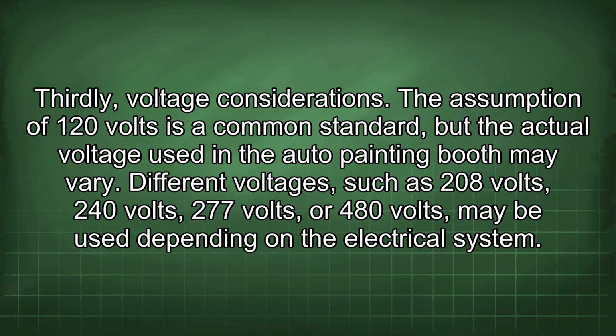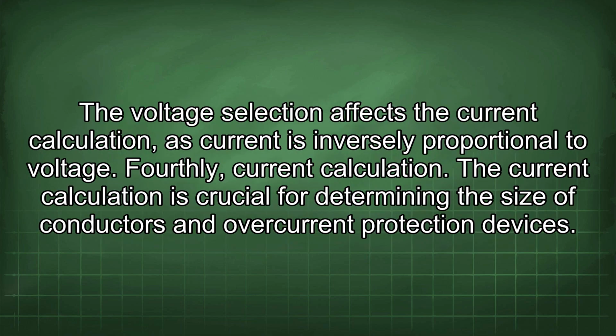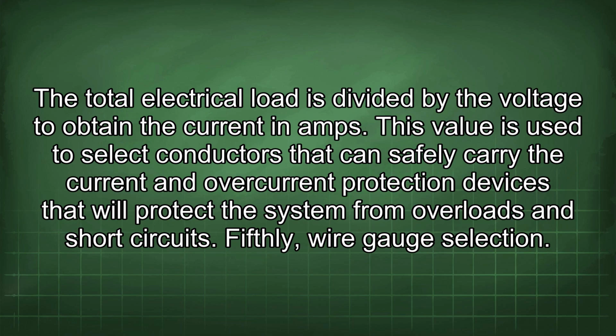Thirdly, voltage considerations. The assumption of 120 volts is a common standard, but the actual voltage used in the auto painting booth may vary. Different voltages such as 208 volts, 240 volts, 277 volts, or 480 volts may be used depending on the electrical system. The voltage selection affects the current calculation, as current is inversely proportional to voltage. Fourthly, current calculation. The current calculation is crucial for determining the size of conductors and overcurrent protection devices. The total electrical load is divided by the voltage to obtain the current in amps. This value is used to select conductors that can safely carry the current and overcurrent protection devices that will protect the system from overloads and short circuits.